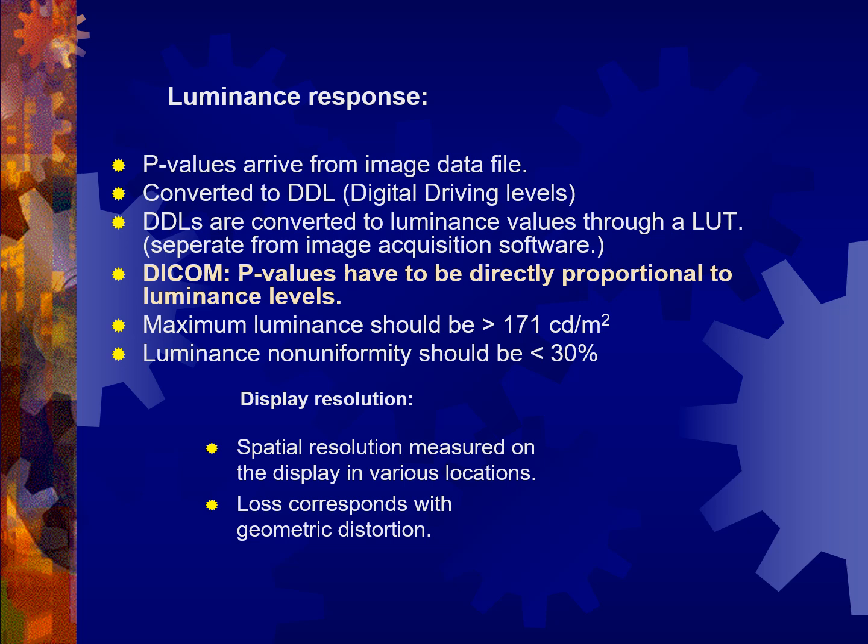You're not allowed to have a monitor display driver that applies an exponential adjustment to the grayscale or to the native p-values. That's a manipulation of the image data, and it affects diagnosis. You can have software that does that, but it's got to be reversible. A monitor display driving software change is non-reversible, so that change is not allowed.